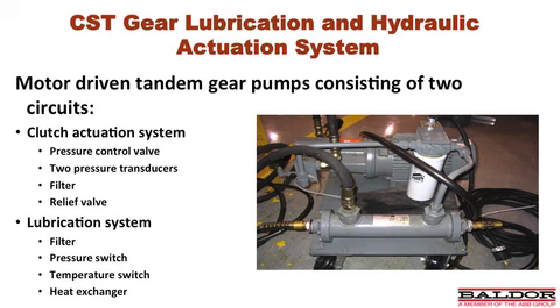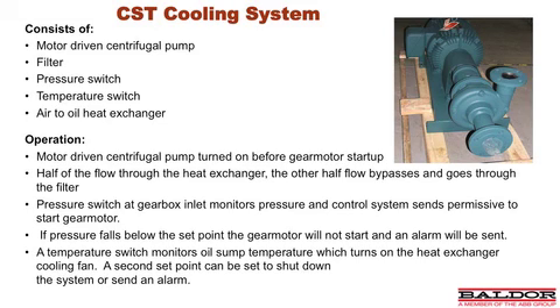The lubrication, cooling, actuation, and electronic controllers incorporate motor-driven tandem gear pumps, and they consist of two circuits. There's a clutch actuation system and a lubrication system. The CST cooling system covers, as I mentioned earlier, the motor-driven centrifugal pump. There's a filter, pressure switch, temperature switch, and air-to-oil heat exchanger. In the operation process, the motor-driven centrifugal pump is turned on before the gear motor starts up. Half of the flow passes through the heat exchanger. The other half bypasses and goes through the filter.